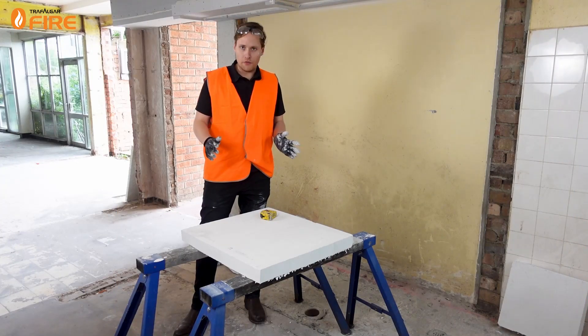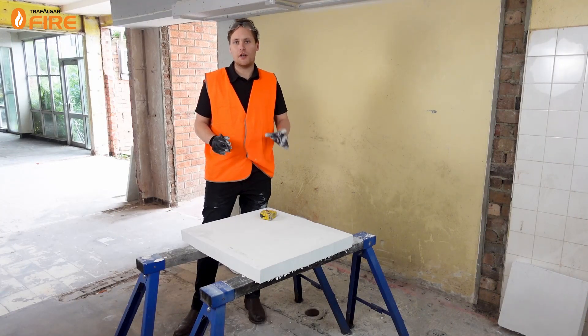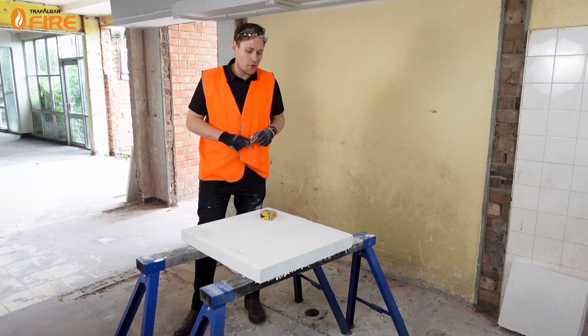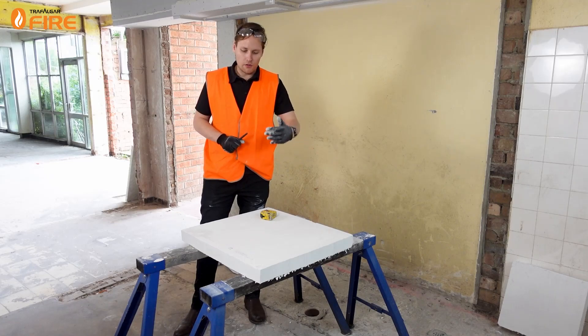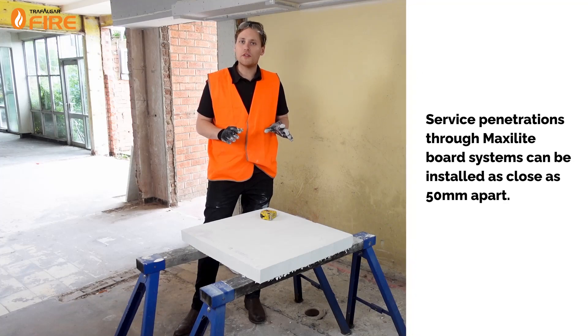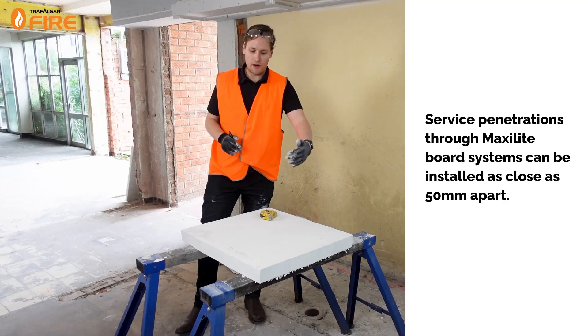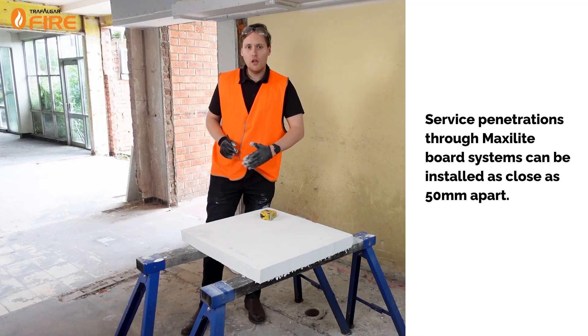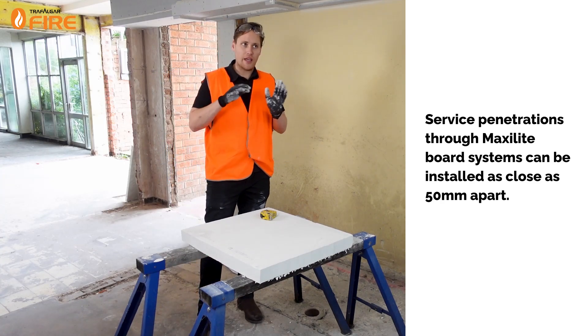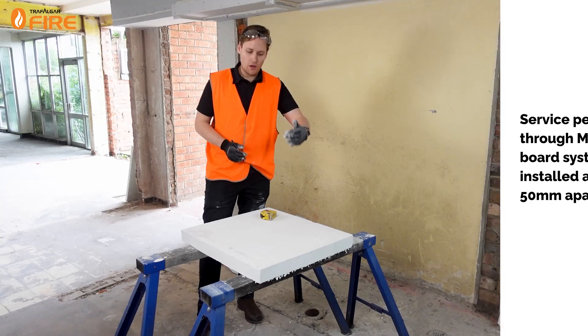I've cut it 100mm oversized to overlap the penetration 100mm on all four sides of the perimeter. Now I'm going to cut the board in horizontal cuts that line up with the services. When you're cutting MaxiLite around multiple services you have to keep all of the cuts parallel — so you get all horizontal or all vertical. In today's challenge we've got a horizontal cable tray so it makes sense to do horizontal cuts.